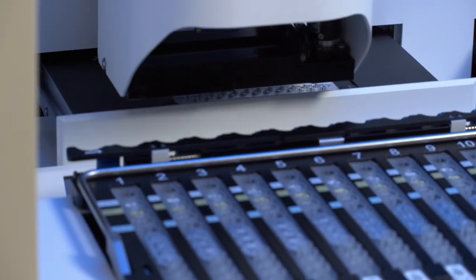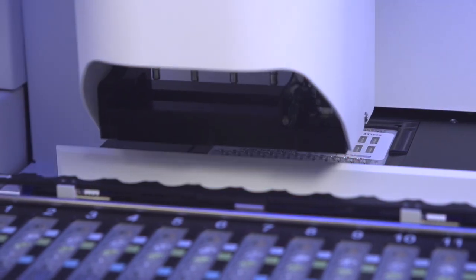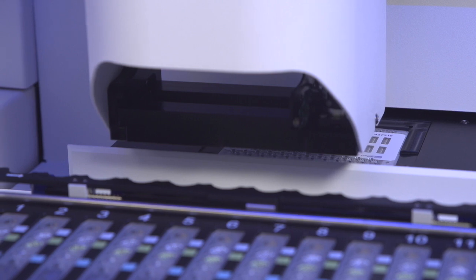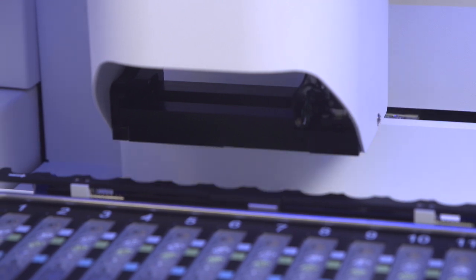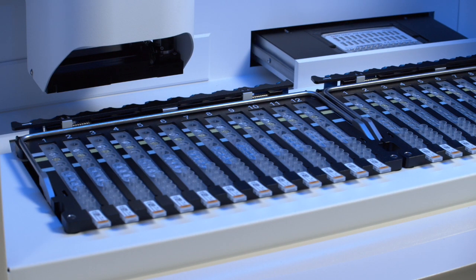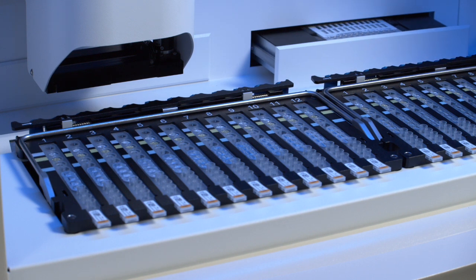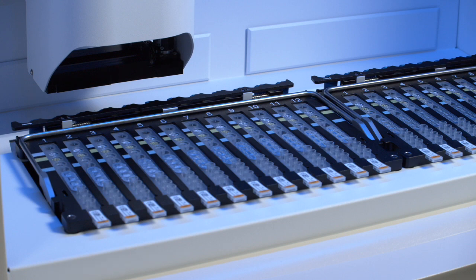The BD MAX system will automatically select the position and row on the BD MAX PCR cartridge for each run. Each rack needs one PCR cartridge to complete a run. Remember, the drawer closes automatically. Don't try to close the PCR cartridge drawer manually.